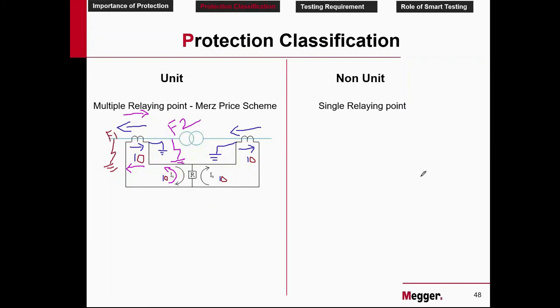Now let us say somebody is placing a bomb outside the hotel. Now what should the security do? It is not inside his hotel boundary. It's not inside the compound wall. He is doing something outside. But at the same time, it is understood that if the bomb blasts, it is going to affect the hotel. So this bomb is actually nothing but the magnitude of the fault current. So what we understand from this example is, if the magnitude of the fault current is very high, then even if the fault is outside the boundary, that is outside F1, still the relay should trip.